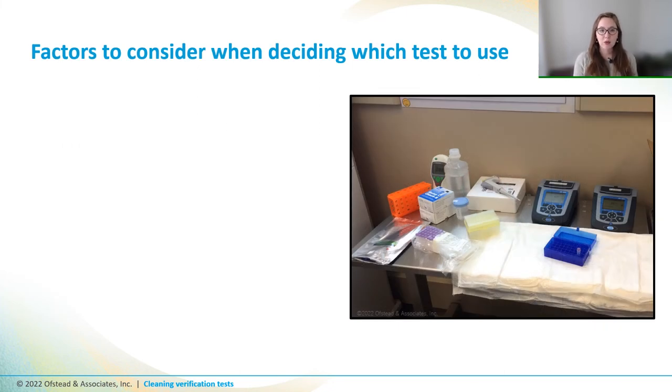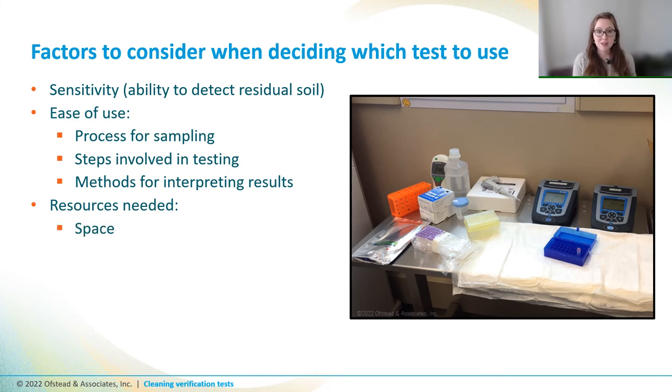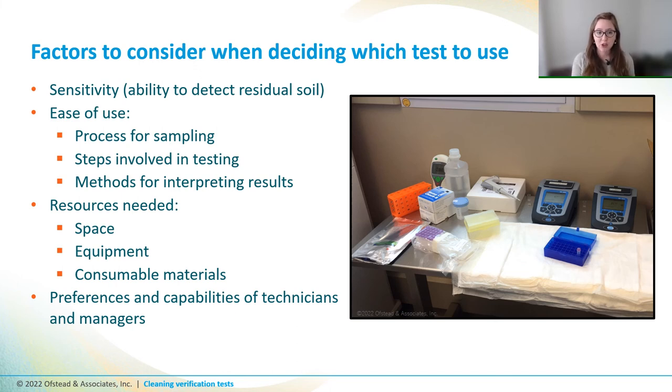So to wrap up, when we're trying to decide which cleaning verification tests to use, there are several factors to consider. First, there's the sensitivity of the test, or its ability to detect tiny amounts of soil. You should also consider the ease of use. And there's three aspects of this: the process for actually taking the samples, the steps involved in the testing, and the methods for interpreting the results, whether it's that quantitative or that qualitative interpretation. You'll also want to consider the resources you're going to need, including space, equipment, and cost, including consumable materials. And lastly, it's important to consider the preferences and the capabilities of your team, the technicians and the managers who are going to be responsible for the day-to-day implementation of cleaning verification testing.